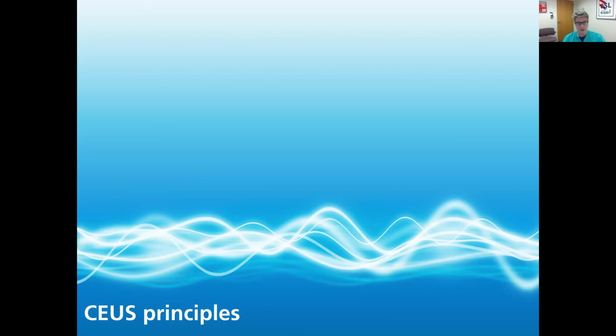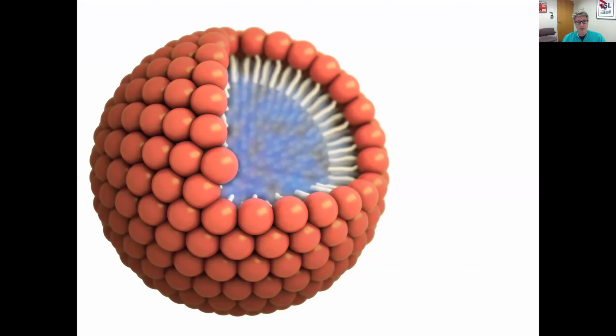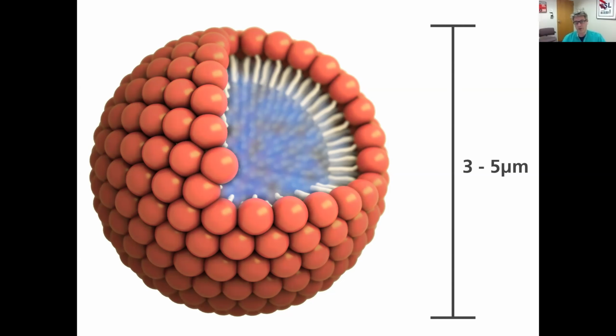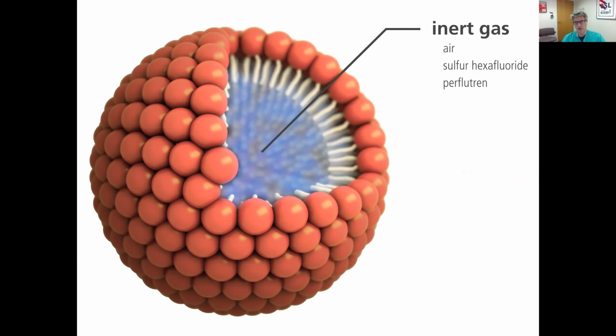So let's talk about some contrast principles, and I assume most people, because it's the Fellows Hangout, have a fairly good understanding of ultrasound imaging in general. So contrast-enhanced ultrasound is based on using little microbubbles. Initially, actually, they used air without any additives, but that dissolves pretty quickly into plasma. So modern microbubbles are about 3 to 5 micrometers in diameter, about the size of an erythrocyte, and they consist of an inert gas. The older generations are air, the newer generations are more the inert gases, so sulfur hexafluoride or perfluorocarbon. And then it has a stabilizing shell, either lipids or albumin or polymer, that prevents it from getting taken up into the plasma immediately, and it makes it survive the transpulmonary passage when you inject it intravenously.